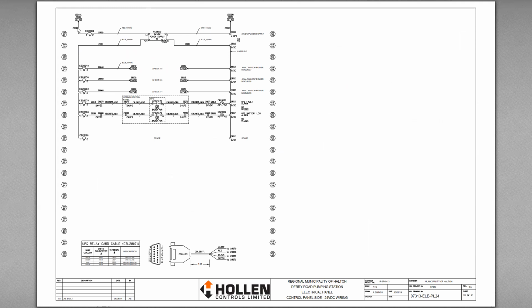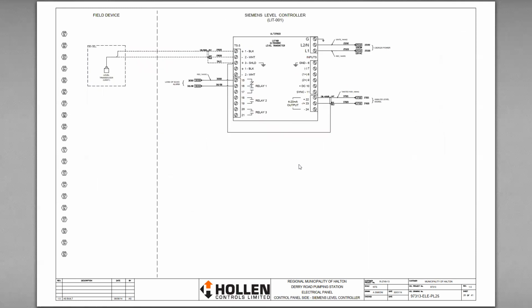24-volt power supply to step down to these contacts for the UPS. Down here, there's a specialty cable for the alarms on the UPS. The Siemens ultrasonic level control transmitter, how to wire its ultrasonic head, where to get its loss of echo, where to get its analog signal, and how to power it.